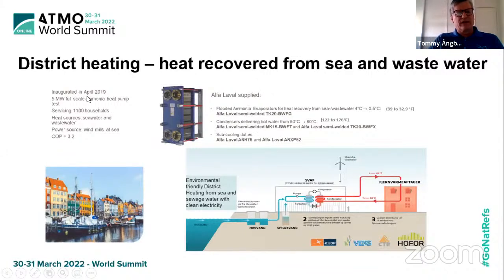This one, for example, was inaugurated back in April 2019 in Copenhagen, a 5 megawatt full-scale ammonia heat pump. They call it a test because the real need for Copenhagen is, of course, much more than that. But this plant was servicing 1,100 households, and the heat source used was seawater mixed with a wastewater stream that would raise the temperature a little bit and help us to get a better COP. The power source for the compressors was windmill electricity, so we could say that it's a completely fossil-free heating, and the COP is 3.2. So for every kilowatt of electricity sent into the plant, you get 3.2 kilowatts of heating out.